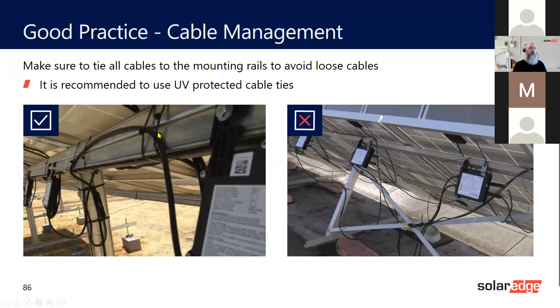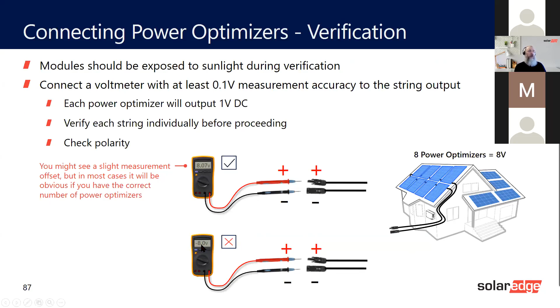Another thing is to make sure that you have the correct polarity. If you connect your test lead with the plus to the right one and the minus to the left cable, you will get the correct polarity. However, if you've got minus, it means that you have the polarity incorrect on one of the cables here, and you're getting reverse polarity. The inverter will not start with reverse polarity. If you have a minus voltage on there, the inverter will not start. Okay?